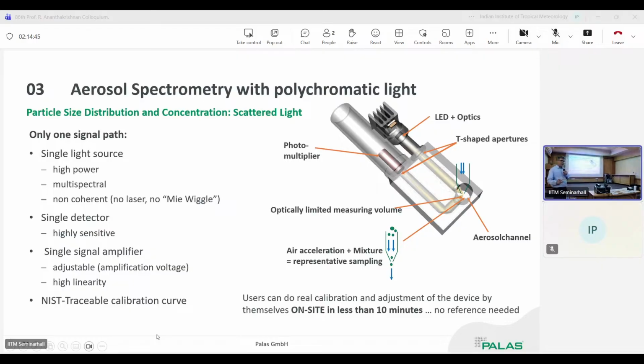Yeah, we can change the size ranges. We typically have 3 to 4 dedicated size ranges for the instruments. For the ambient air measurement of particulate matter for the regulatory module, it's typically up to a maximum of 20 micrometers, starting from 175. Most of the particles are around 200, 300 in number concentrations, but the big particles are also very important because they dominate the mass.